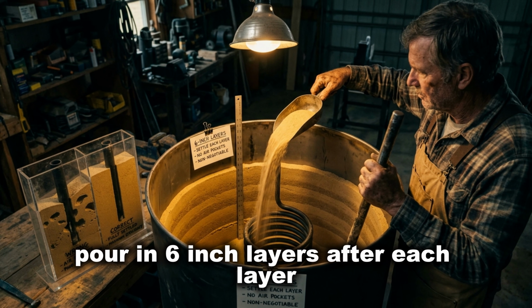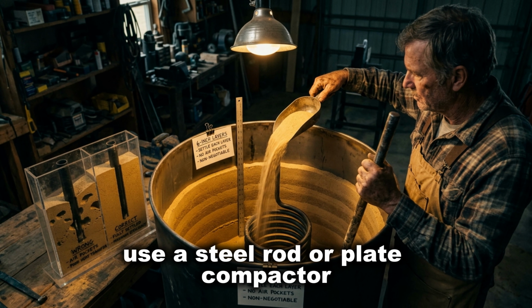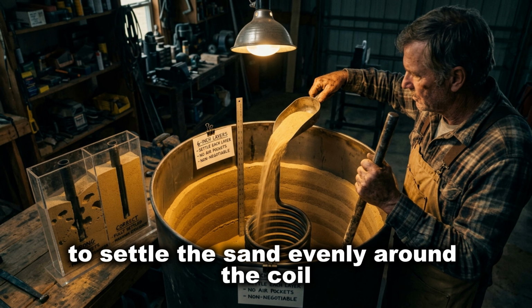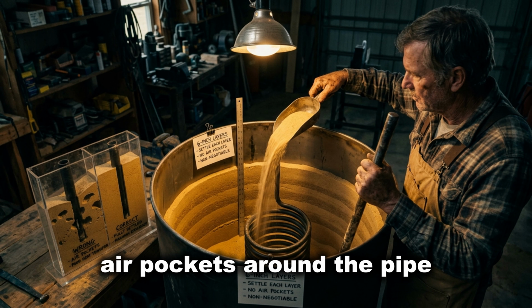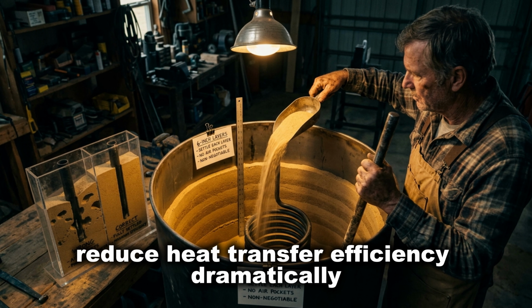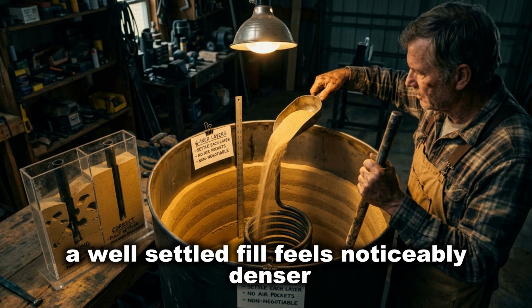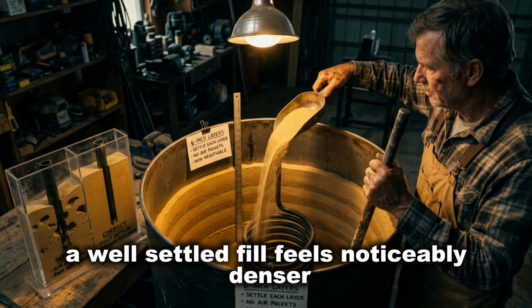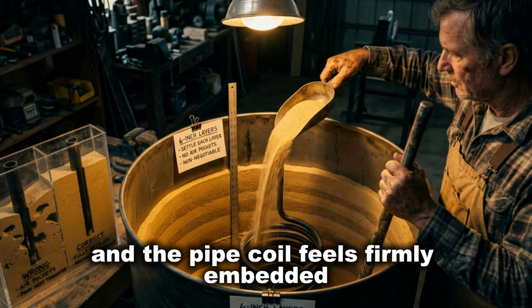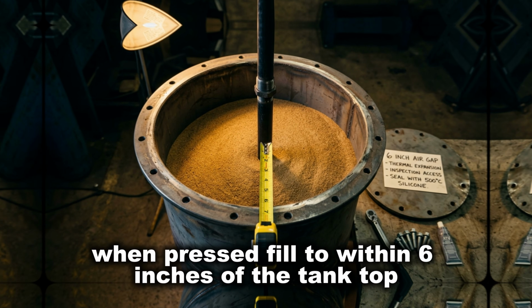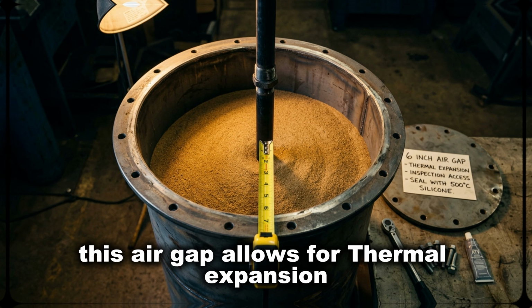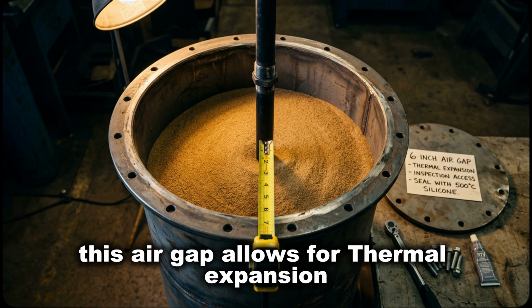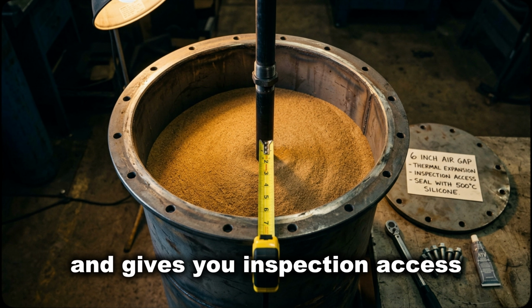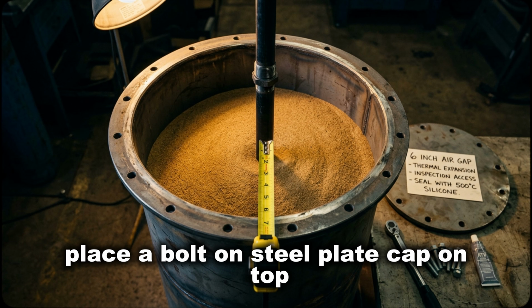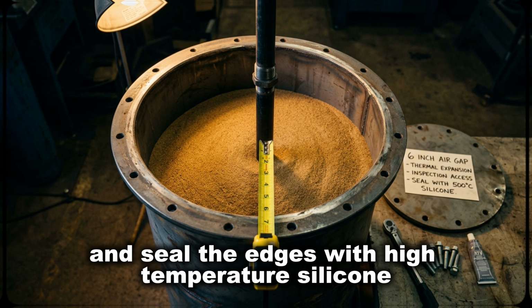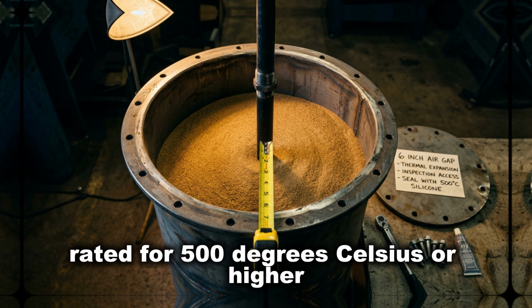Pour in 6-inch layers. After each layer, use a steel rod or plate compactor to settle the sand evenly around the coil. Air pockets around the pipe reduce heat transfer efficiency dramatically. A well-settled fill feels noticeably denser, and the pipe coil feels firmly embedded when pressed. Fill to within 6 inches of the tank top. This air gap allows for thermal expansion and gives you inspection access.